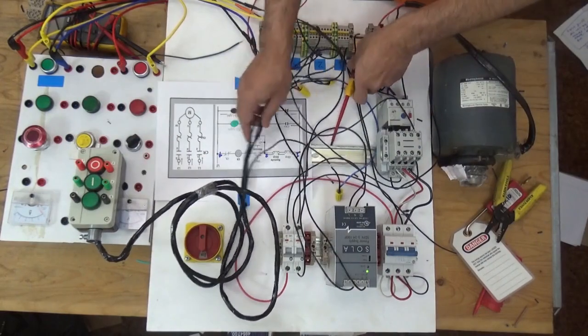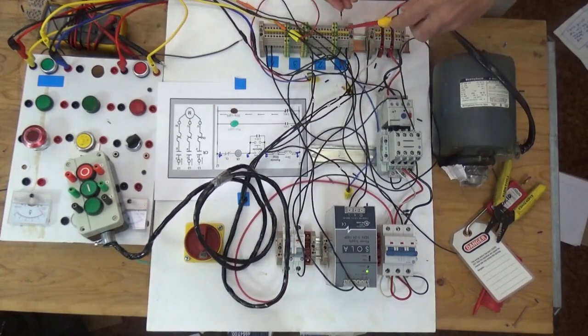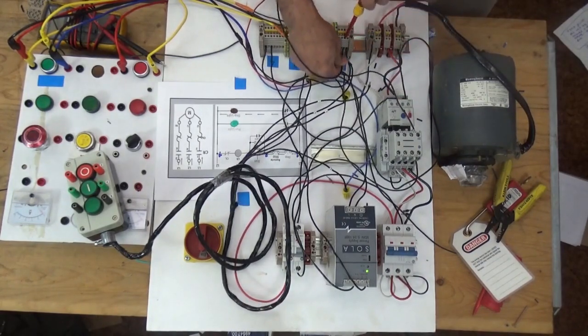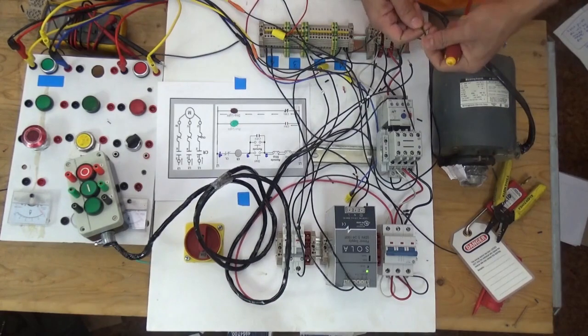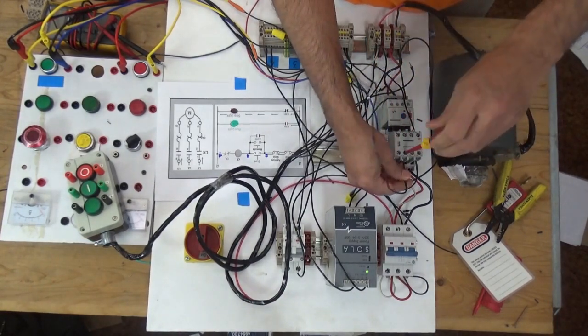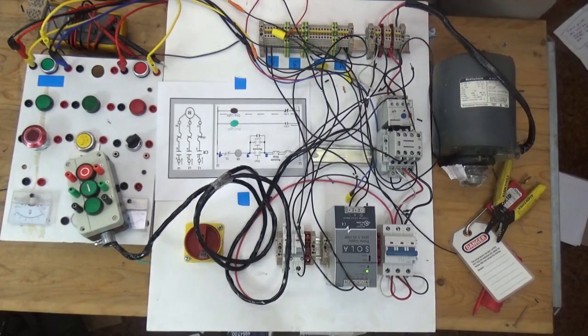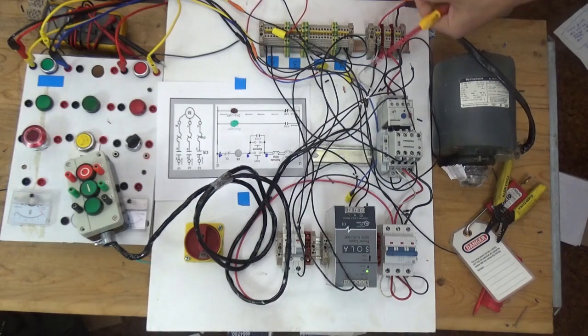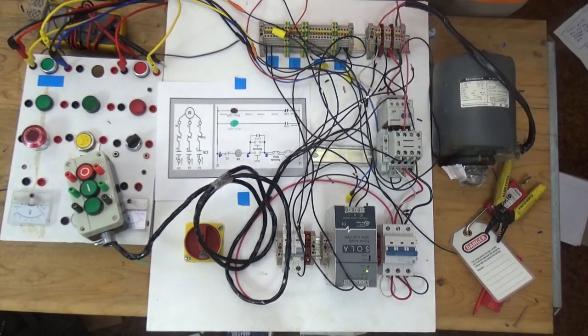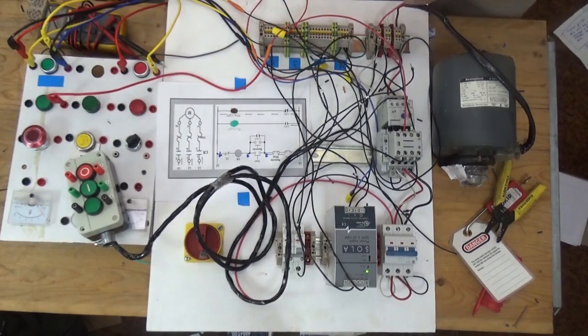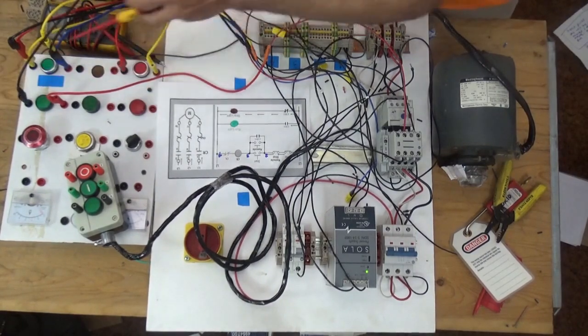So that is multiple start-stop. Now the next one is we're going to connect the indication light from line one going to our normally open. From normally open going to our lights, start. And from lights going to line four here.